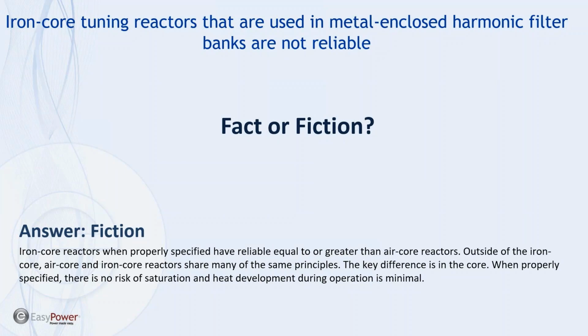The voltage across the reactor is just 1 over N squared times the line to neutral voltage of the system. So a 5th tuned reactor on a 13.8 kV system, at 7960 volts line to neutral, will see just 1/25th of that. So on the order of say 500 or 600 volts, not a whole lot of volts across the iron core reactor. Therefore, under normal conditions, it's just not stressed.